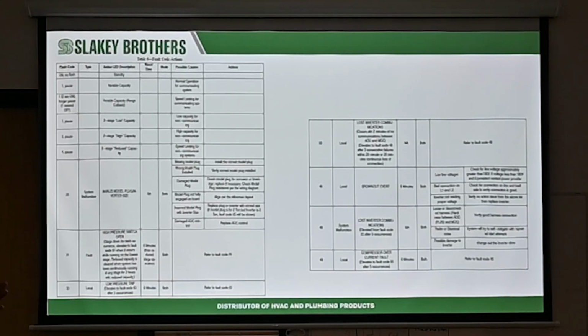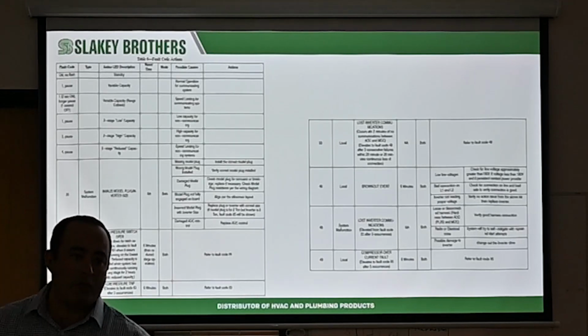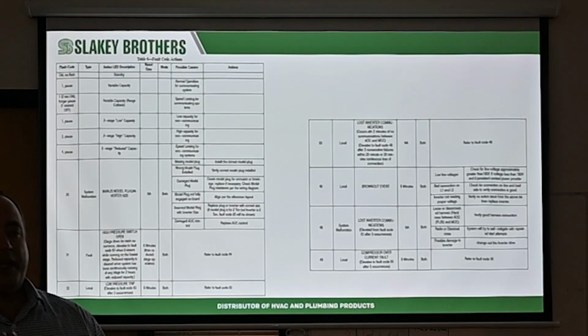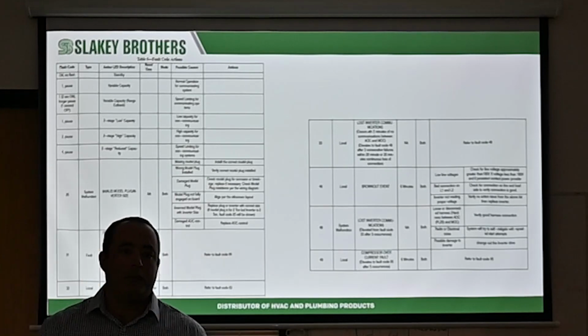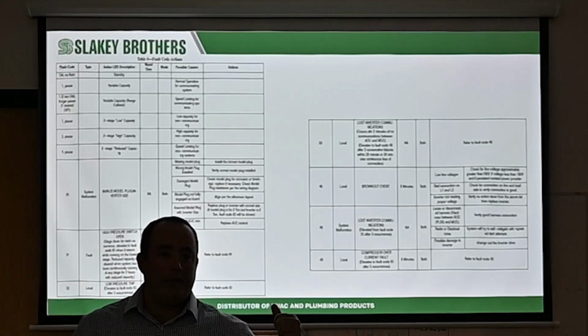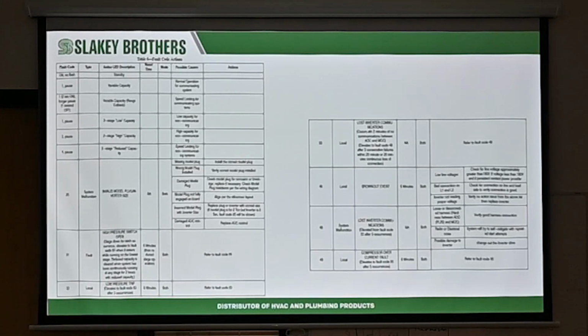When anything does go wrong, realistically, it's one of a few little things. You have to replace a board, or a compressor, or a motor. It's simple. Even though there's all this fancy stuff right here, if your inducer motor doesn't work on a regular unit, what do you do? You check for voltage, capacitors, play on the bearings, junk that motor, put another one in there. These things do a lot of the work for you. That's why they're so intimidating, but they do so much work for you. Off of a simple diagnostic code that tells you, hey, there's a problem with the inducer motor, or the high pressure switch, maybe the inducer motor isn't working. These things know what's going on.